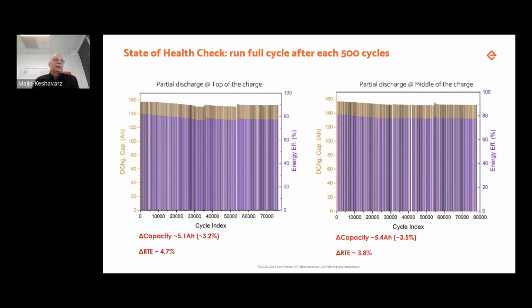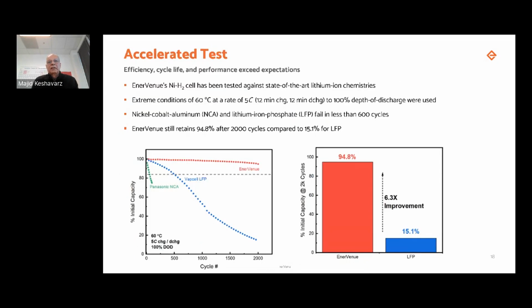So the way we check this state of health, every 500 cycle, we do a full cycle, 0 to 100%, and look at the capacity, voltage, etc. And what we are seeing now after 80,000 cycles, we're losing about 3.5% in capacity, and the round trip efficiency drops 3 to 5%. And this is very encouraging results that we are seeing here from this type of battery. We're doing it at different temperatures, different conditions, but this is representative of one of the accelerated tests.